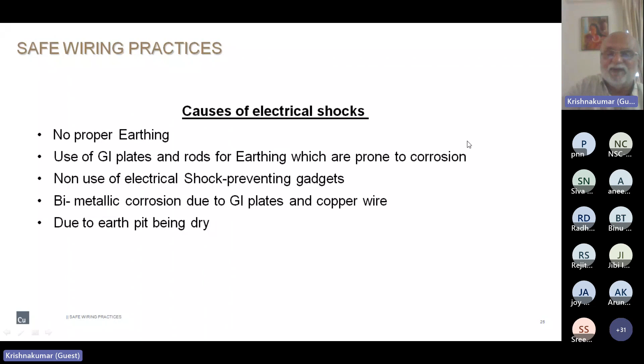These things can be avoided by using the same metal, preferably copper, because copper has more resistance to atmospheric deterioration. It can last at least about 15-20 years if a proper plate or sufficiently coated copper tubes are used. That will be the earthing. You need to keep this in mind.